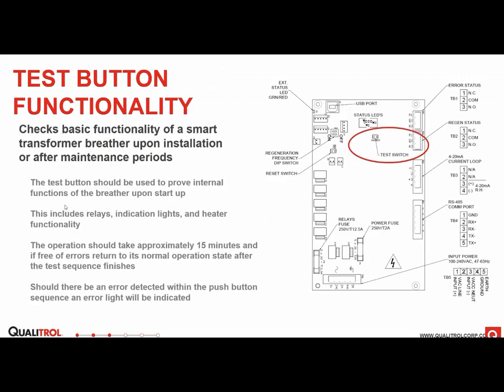So a big feature that we added to our Gen 2 breather is a test button functionality. What the test button does is that it essentially checks all of the system statuses. So it makes sure your pressure sensor is working, your RH sensor is working, your solenoid works, and it also checks that the heater is working. So this takes about 15 minutes.